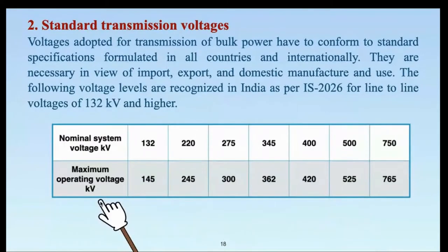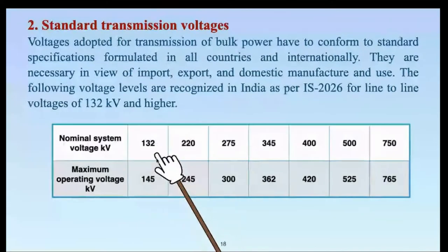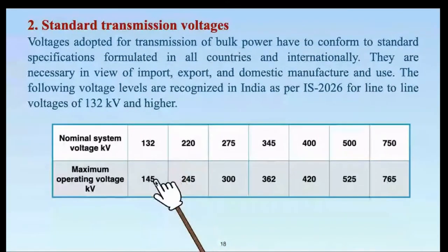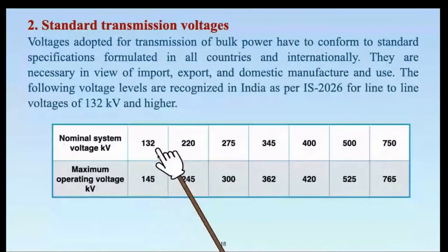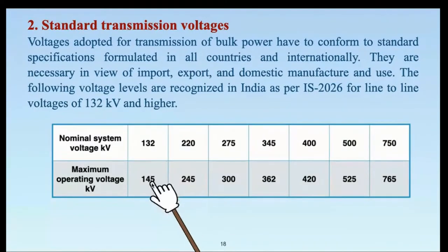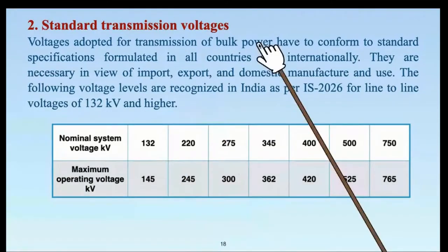The next parameter explained is maximum operating voltage. If you try to find the ratio: a 132 kV line will have a maximum operating voltage of 145 kV — these are also specified as a standard. The difference between 145 kV and 132 kV is around 10 to 11 percent higher. So 145 kV is about 10 percent higher than 132 kV, this being the entry-level bulk power transmission voltage.